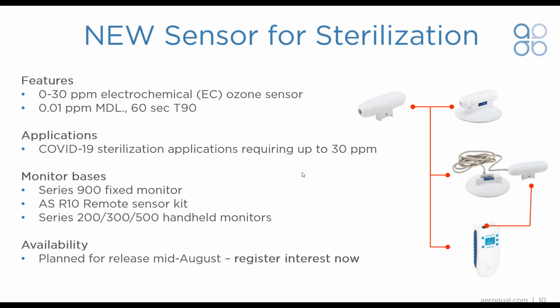As I mentioned on the previous slide, the EC sensor is ideal for measuring ozone levels above 0.1 ppm. Many sterilization applications we've typically been associated with have only required a sensor up to 10 ppm. Since COVID-19, we've received a lot more requests for a sensor with a range up to 30 ppm. These applications involve a high level of ozone for a short duration, like a short, sharp shock treatment, as people sometimes call it.